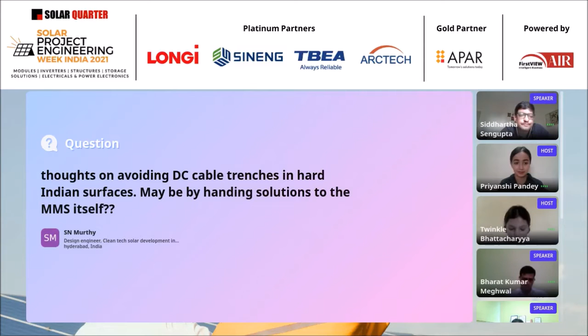There are definitely cable tray solutions which many of the projects we have implemented use. But the cost of cable tray is higher compared to a normal cable trench or buried cable trench. So another solution coming up is cable hangers, as the question itself asks. There are solutions where the module cables and certain string cables can run along the MMS structure using a specialized cable hanger solution.